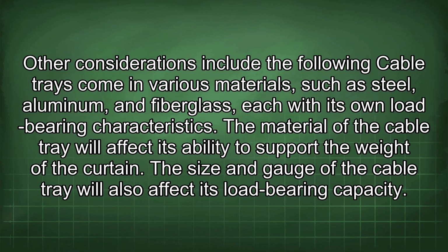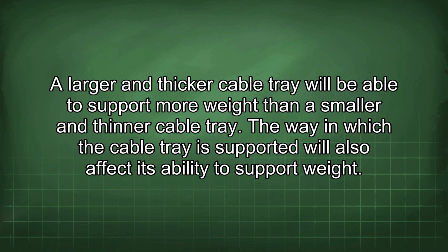Cable trays come in various materials, such as steel, aluminum, and fiberglass, each with its own load-bearing characteristics. The material of the cable tray will affect its ability to support the weight of the curtain. The size and gauge of the cable tray will also affect its load-bearing capacity. A larger and thicker cable tray will be able to support more weight than a smaller and thinner cable tray.